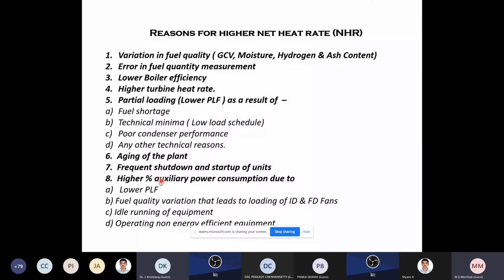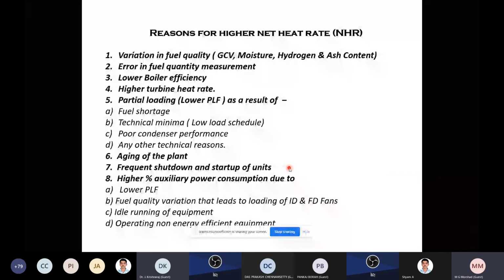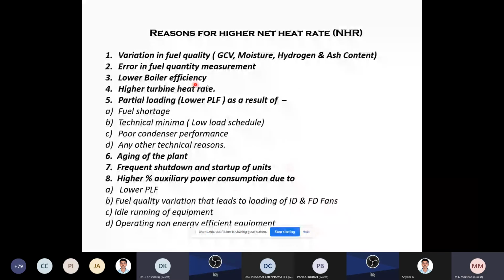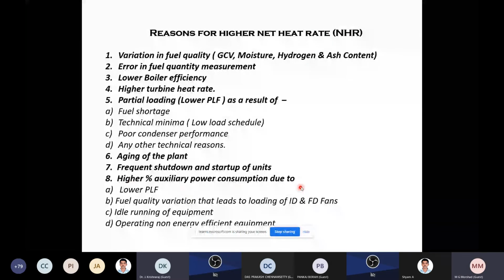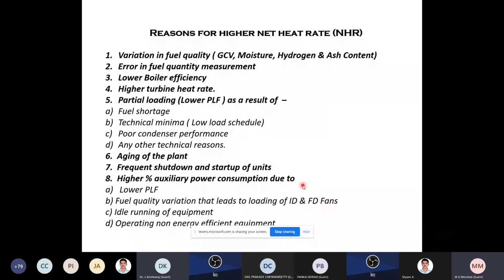Then the aging of the plant is also one of the reasons for the net heat rate. Frequent shutdown and start of the unit, so very frequent tripping of the unit. In such a case also the net heat rate will increase. Higher percentage of auxiliary power consumption: if the percentage of auxiliary consumption is higher, that also leads to a higher net heat rate. So it is for what reason?